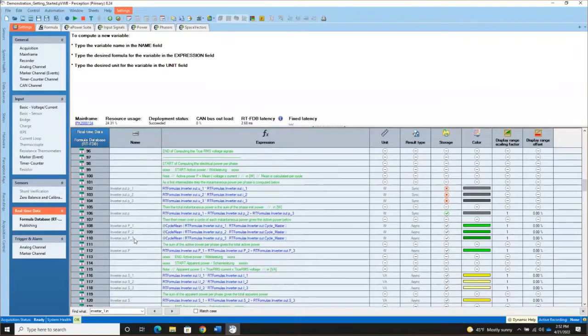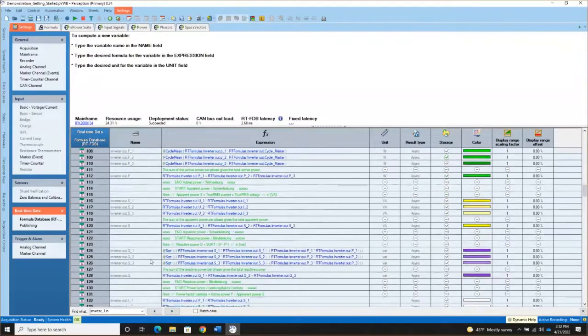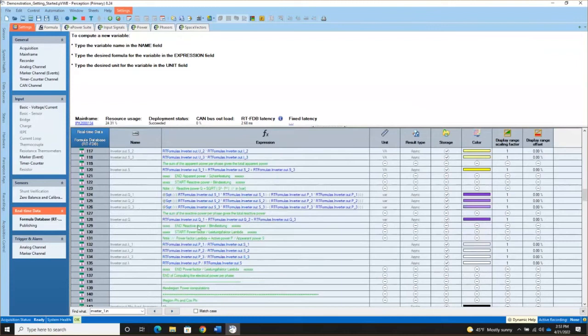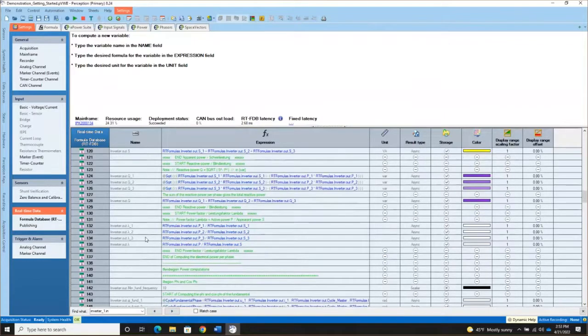We also find the cycle-based mean of each phase and sum them together to find the total active power. Apparent power is calculated from the RMS of voltage times the RMS of current — done for each individual phase and summed for total apparent power. Reactive power is calculated from apparent power and active power: we square the apparent power, subtract the square of the active power, and take the square root, done per phase and summed for total reactive power. Power factor lambda is the active power divided by the apparent power, found per phase and total.